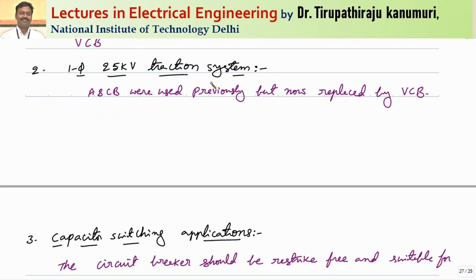For electric traction, there are two aspects: the traction substation supplies power at single-phase 25 kV, and there is also a circuit breaker inside the locomotive collecting current from the supply. Whenever you want to disconnect from the supply, the circuit breaker operates first. Previously, air blast circuit breakers were used for these applications, but nowadays they are replaced by vacuum circuit breakers. The advantage of vacuum circuit breakers is very small size, less maintenance, and far more efficiency when compared to air blast circuit breakers.